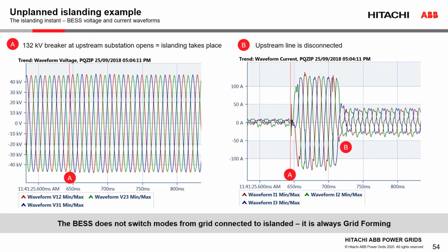Throughout this sequence, the converter is always in grid forming operation, and the reason it is able to do this both in parallel with the NEM and islanded is because of the critical virtual synchronous machine layer. This layer allows the grid forming converter to operate in parallel with the grid. Again, you can see because the converter is providing a voltage sinusoidal waveform on the left, the current is a consequence of the scenarios that occur and hence give it a very fast response when you look at the time step on the x-axis and the speed of response of the current waveform.